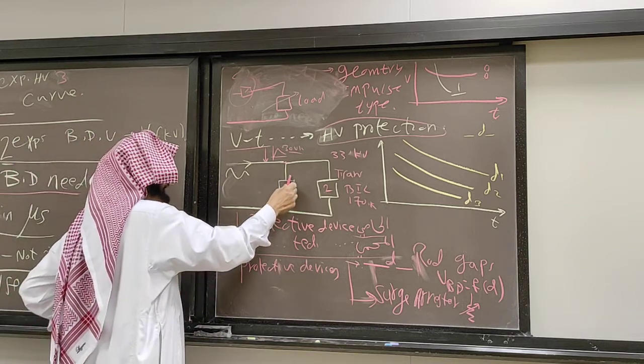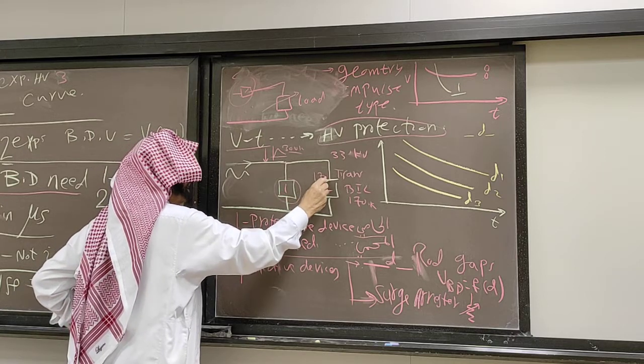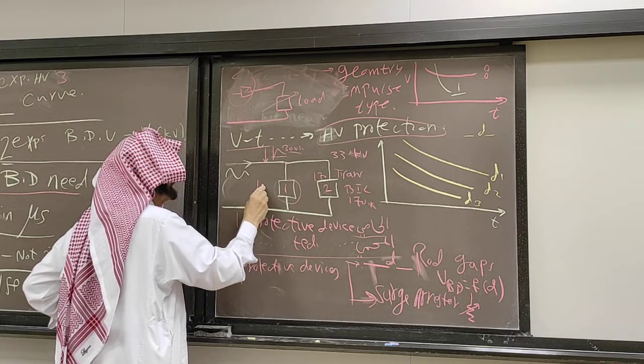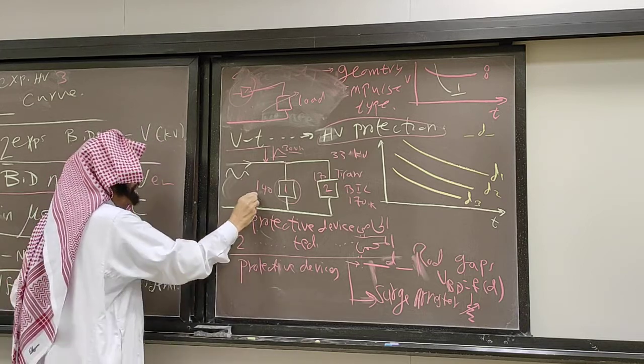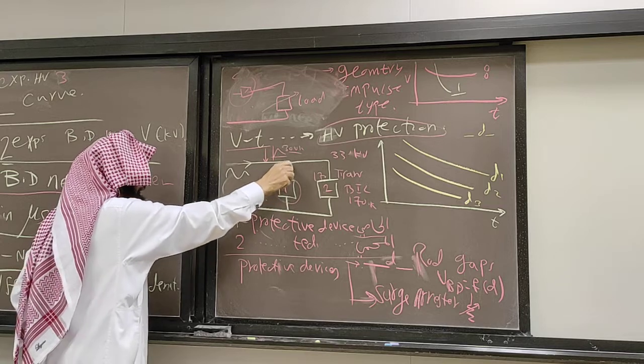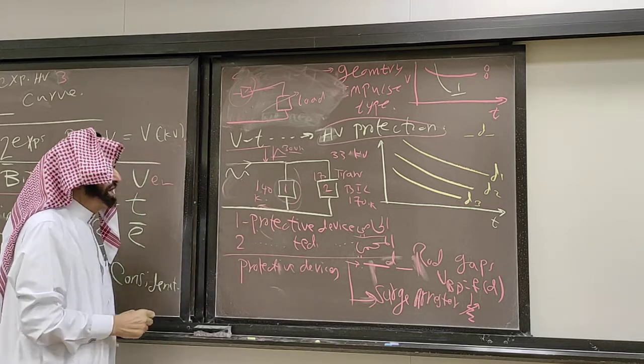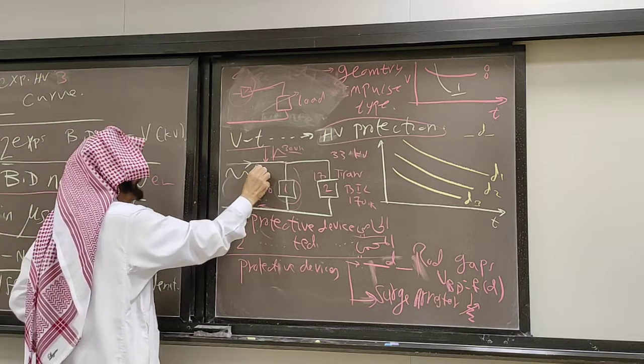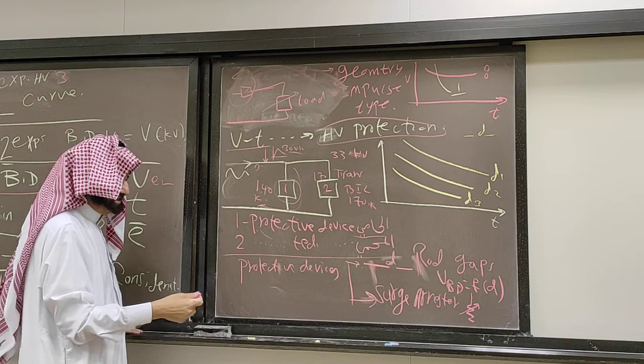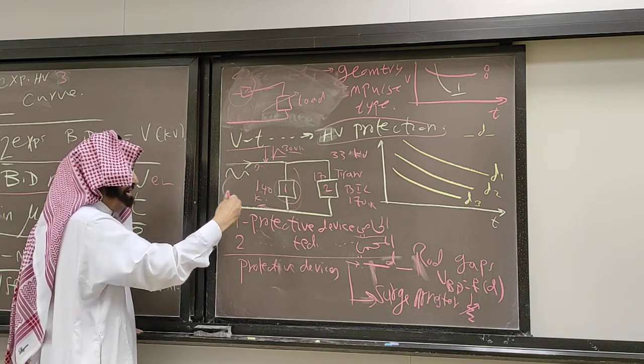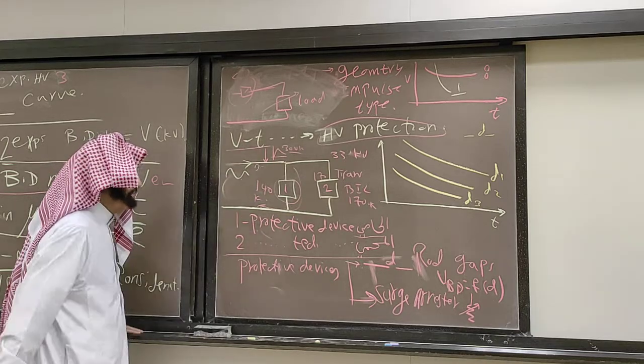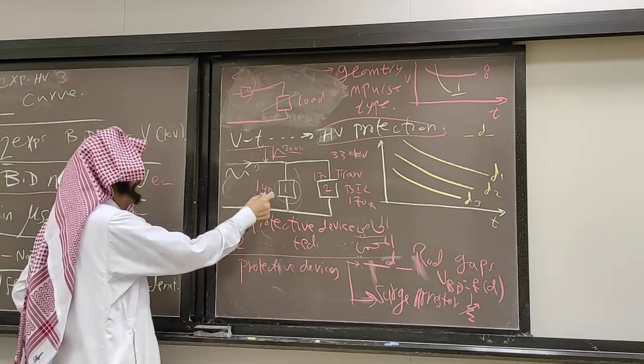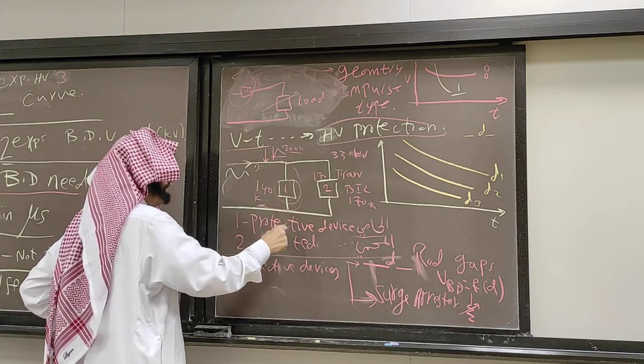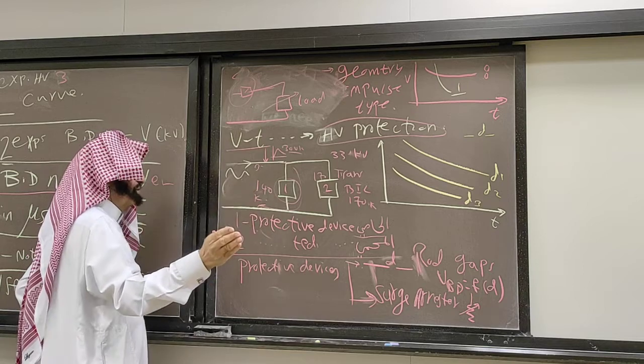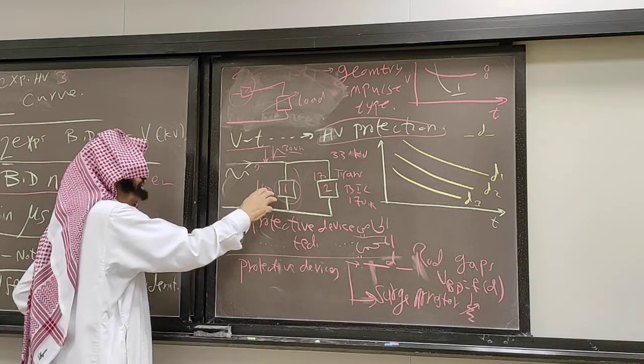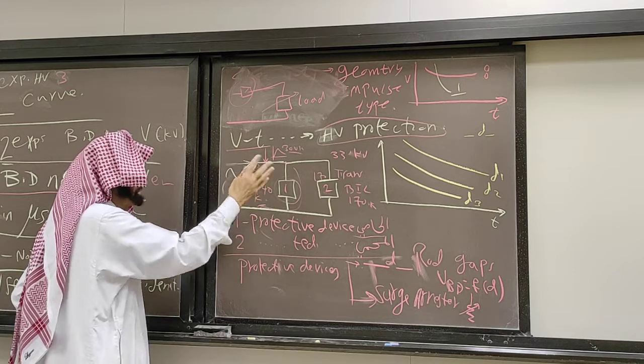So this one, for example, will take 170. So I will make this one work at around 140 kV. So anything more than 140 should come here and go to the ground instead. Of course, if you have 33 kV, you will not set it at 40 or 50 kV. That would make it sensitive. Any small transient will cut it. No, you have to be in the middle. You have to have some range, 30 kV, 40 kV, 25 kV, just to make sure, because this is, as we did last time, statistical. This may be between 130 and 150, so you design it for 140.